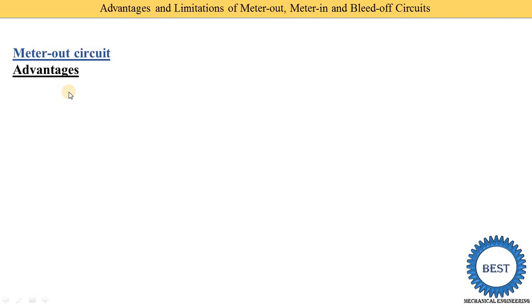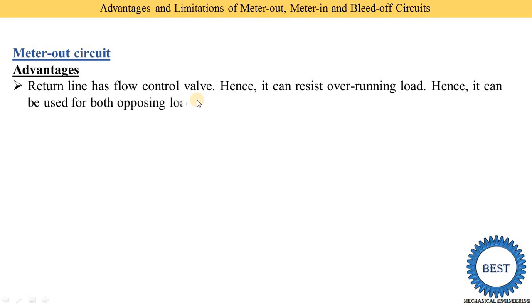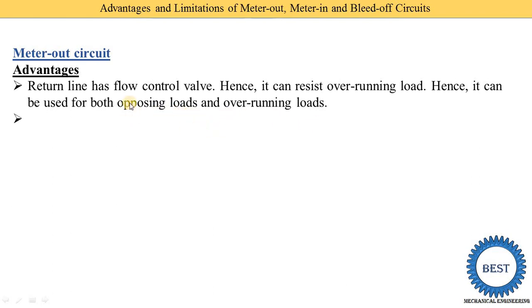In a meter out circuit, the flow control valve is installed at the outlet of the extension as well as the retraction strokes. So the return line has a flow control valve, hence it can resist overrunning load. Hence it can be used for both opposing loads and overrunning loads. This is one of the advantages.